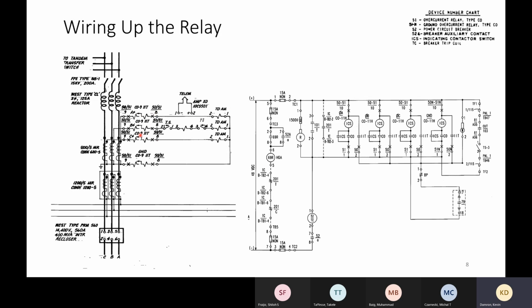So if any of these relays operate, this is the 3 line and the AC portion of it. If they operate, we'll say that there is a fault. So in that case, my CO would operate. So here we've got plus and minus 48 volts. If it's an A phase to ground fault, if we put a fault down here somewhere, then my CO, the relay closes its contact when it times out. At that point, current's going to flow, come down through here, energize my trip coil, and then I'll open my breaker.